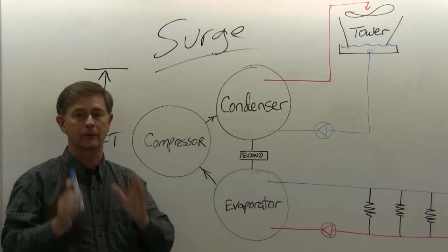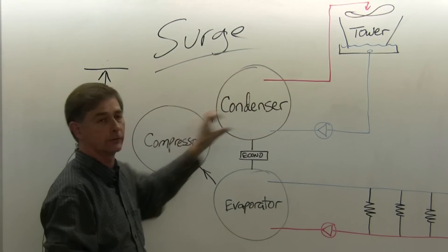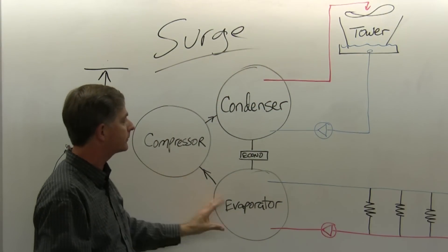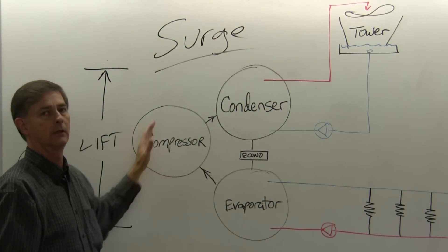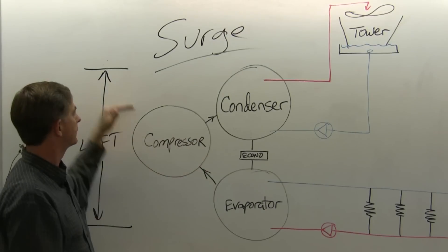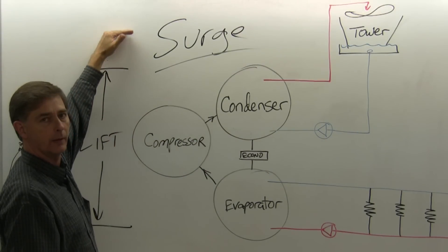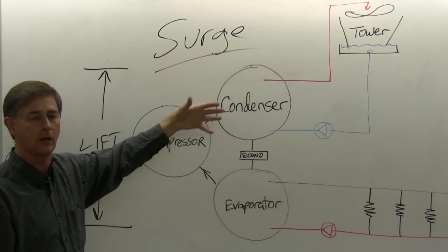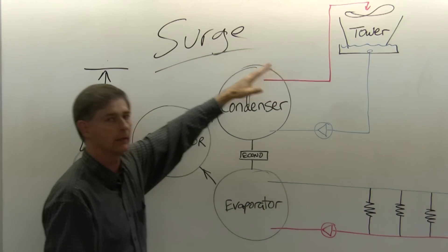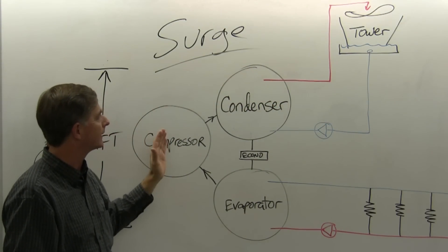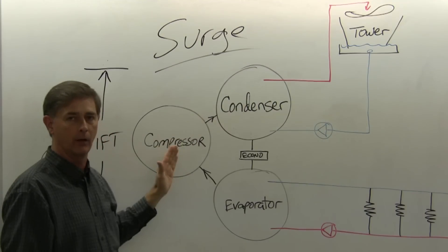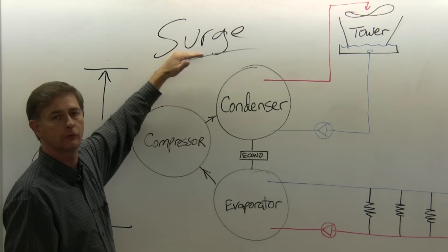Now that condition, that backward flow is a temporary flow, because as it does that, the differential pressure comes in line, and so now it's pumping again. Until it starts to build that pressure differential where it cannot pump against, and you have a backward flow again. That backward flow is called surge.